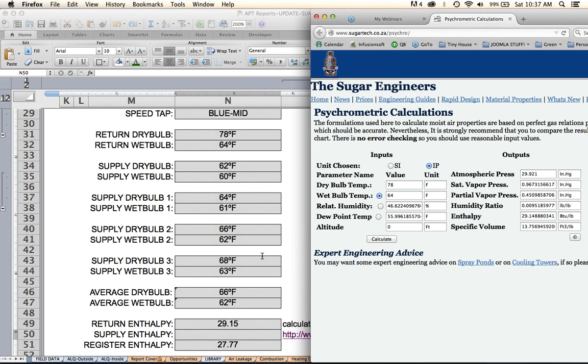And the supply enthalpy, by the way, just as a side note, is the kind of combination. If you look at a psychrometric chart, which has seven axes on it, it's pretty awesome. You need two axes to figure out what the enthalpy is. So you can use dry bulb and relative humidity, as you can see here, or dew point temperature. So if you've got a thermometer that already does one of those and it doesn't happen to do wet bulb, that's okay. You can use any one of those things. Basically, you want to get the sensible temperature, the heat, and also the moisture.